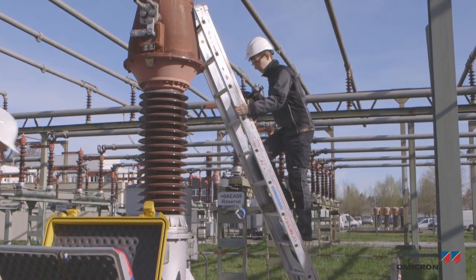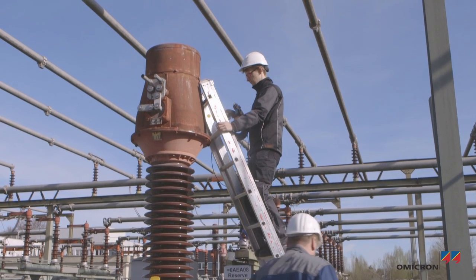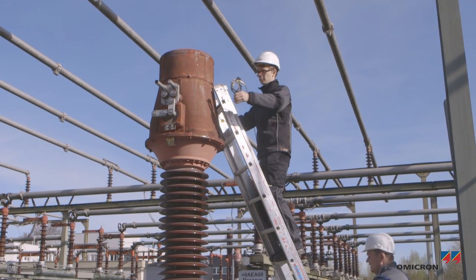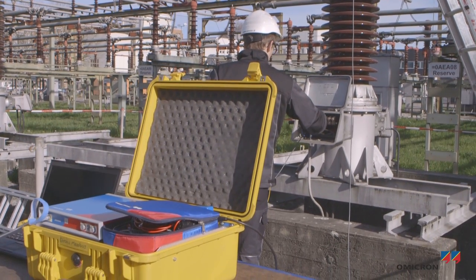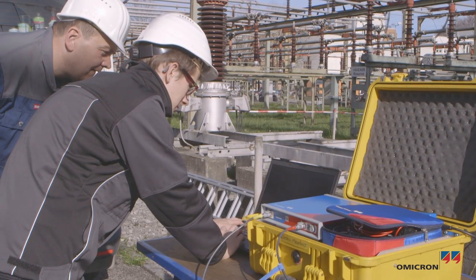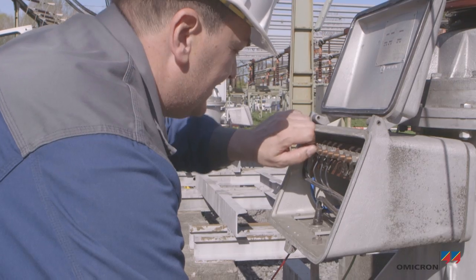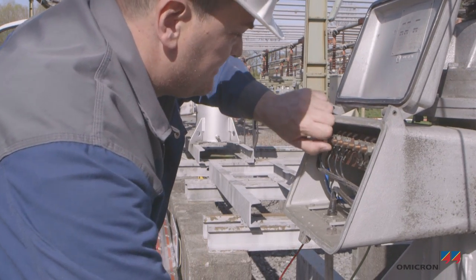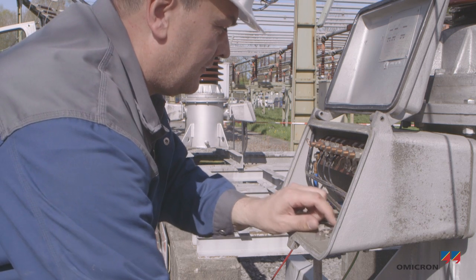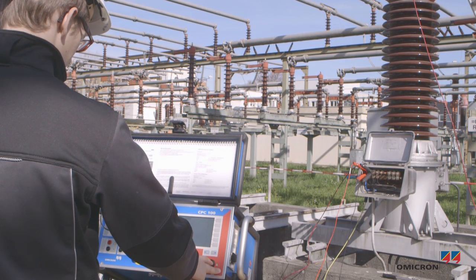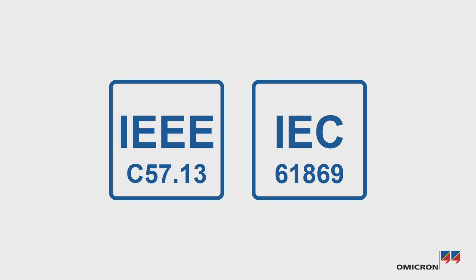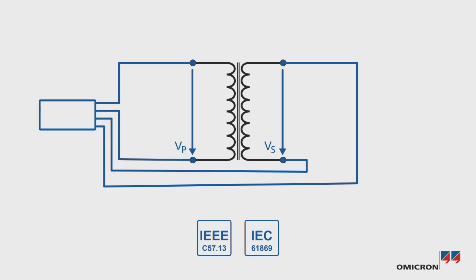Partial discharge measurements may be performed to verify the integrity of the voltage transformer. A detailed analysis of the insulation condition can be obtained through dielectric response measurements. Short circuits can be detected with ratio measurements. However, simple ratio measurements cannot be used to verify the accuracy according to the standards, as the excitation voltage is too low and the burdens defined in the standards are not available.